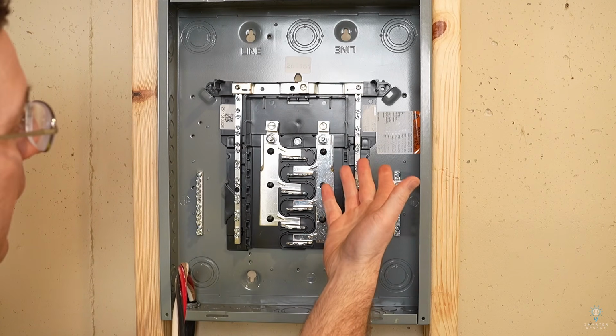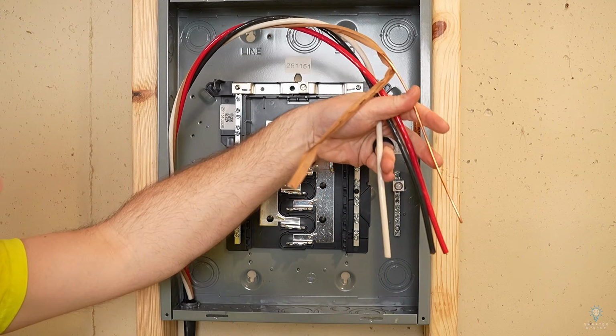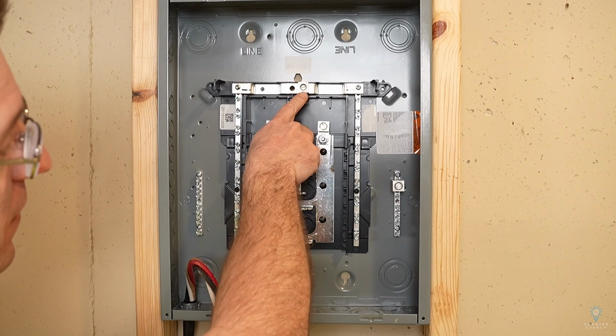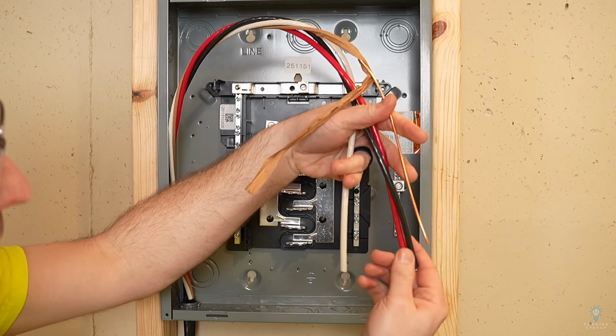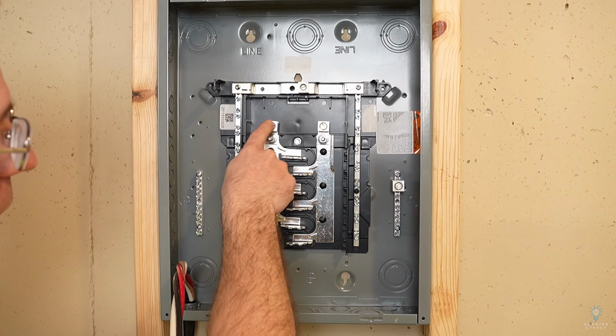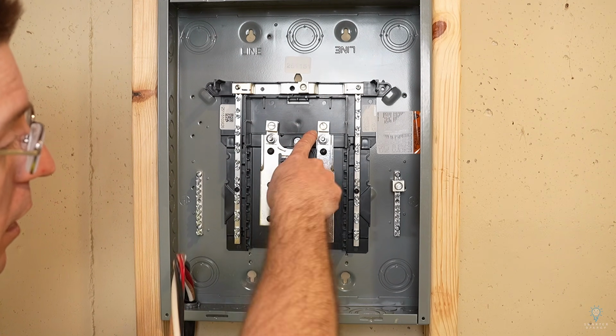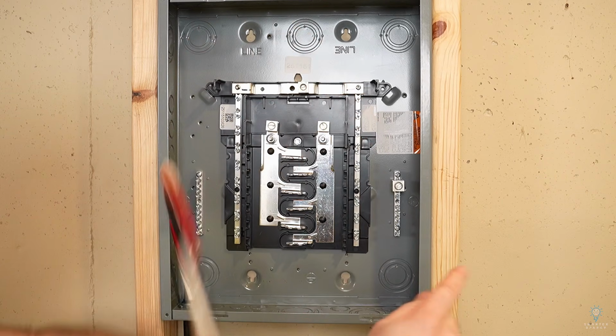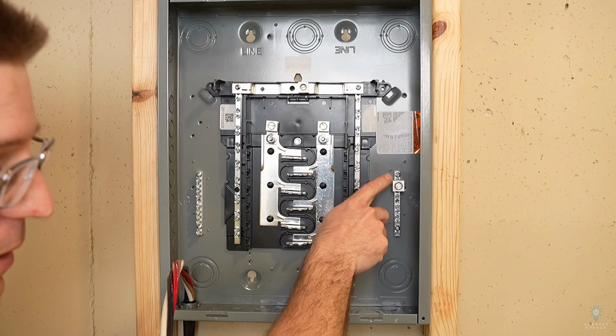And now we've got a spot to land all 4 of our wires here. We've got our neutral that's going to land on this lug right here. We've got 2 hots, and these hots are going to land directly on the lugs for the bus bar. And we've got a ground wire here that's going to land over here on this ground lug.